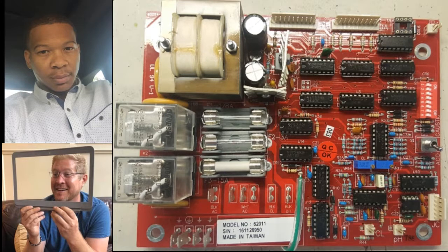With the caustic, that's because we're marketing this controller to the pool industry as a whole. Aquasol's operating area is really along the Gulf Coast. We're using bleach. Bleach has a high pH, so we're going to feed acid to control the pH. But in some areas, they might use, say, trichlor or dichlor with a low pH. I suppose they could even use gas chlorine. We have a line of gas chlorine controls. Correct. So that would be for feeding a caustic, because their sanitizer would naturally bring the pH down, so they bring their pH up. Is that correct?